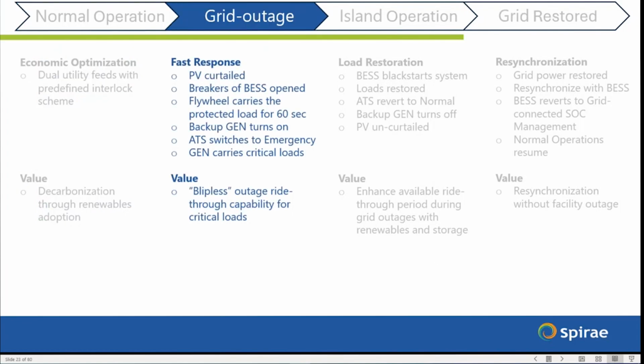Now, let's observe how the system fast responds during an unplanned grid outage. The site constraint is that all renewables and other production resources must be halted during grid outage. Therefore, you will notice the PV output drop to 0 and battery breaker open. During this period, the critical load is temporarily supported by flywheel until the backup generator comes online to take over.